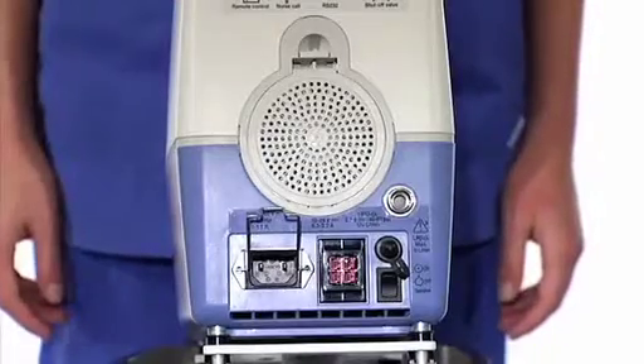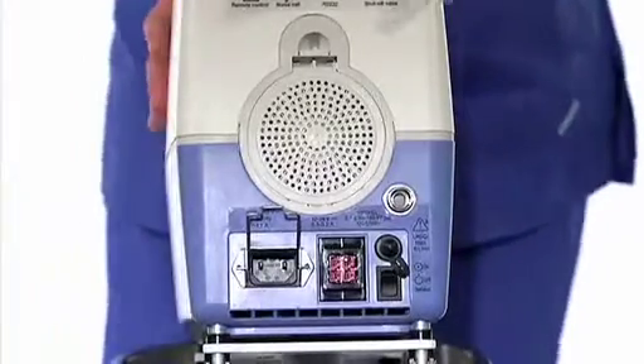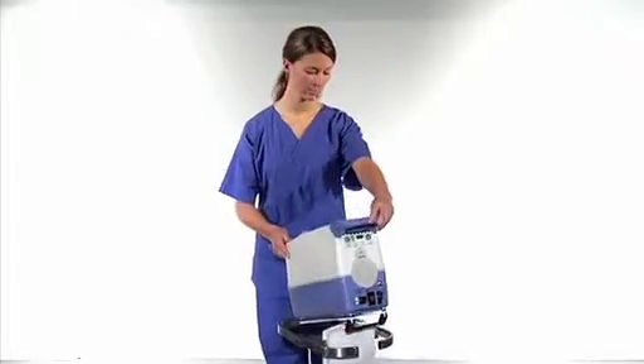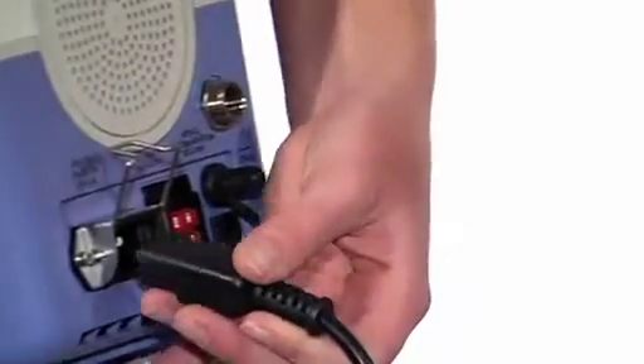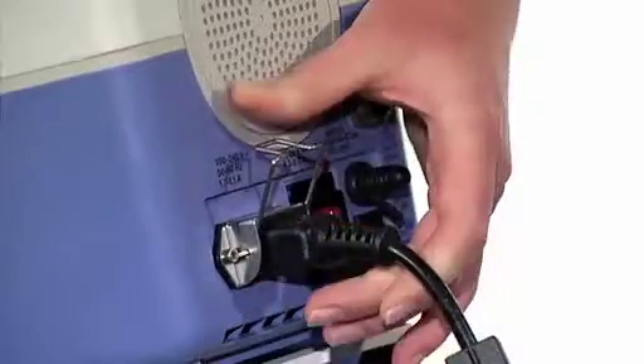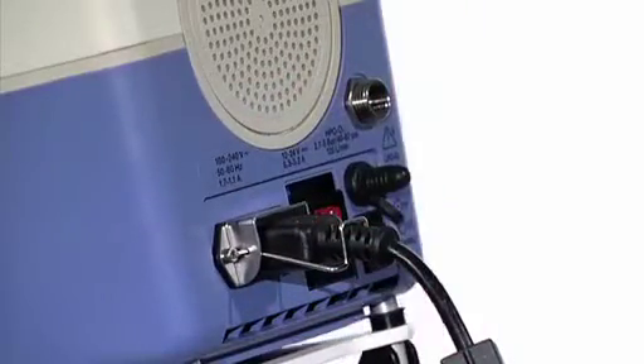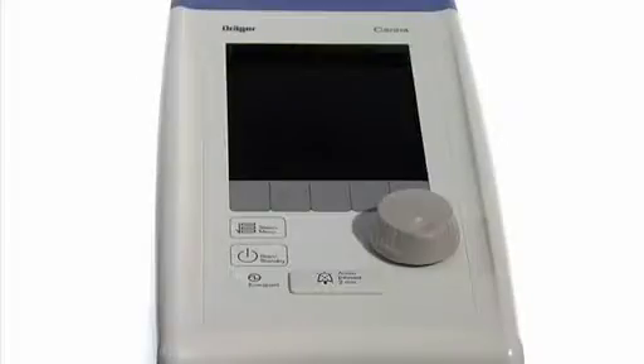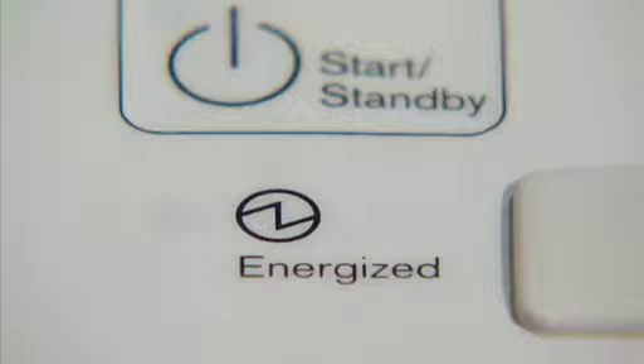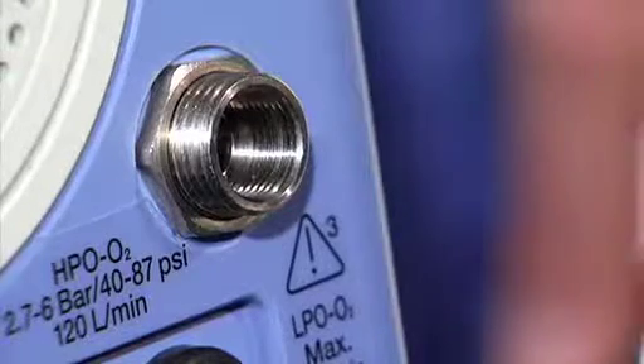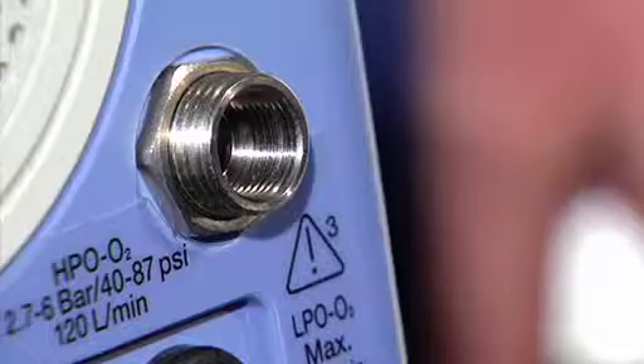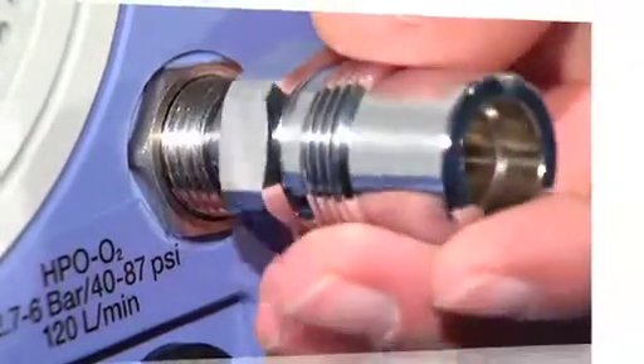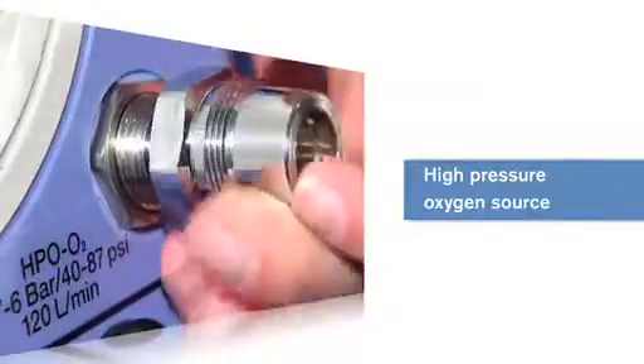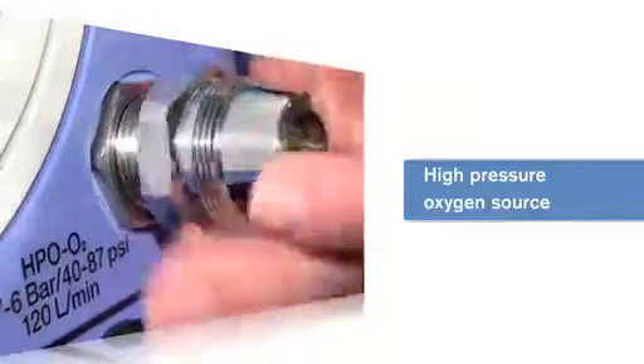Carina needs to be plugged into the mains power for normal use and to charge the internal battery. Please insert the power cable into the device and secure it with the wire clip. The LED on the front panel will flash when the internal battery is charging. Different sources can be used to supply oxygen to the patient. The first is by using high-pressure oxygen via oxygen cylinders or a central gas supply.